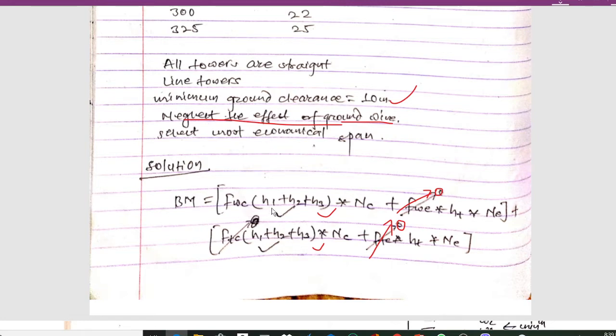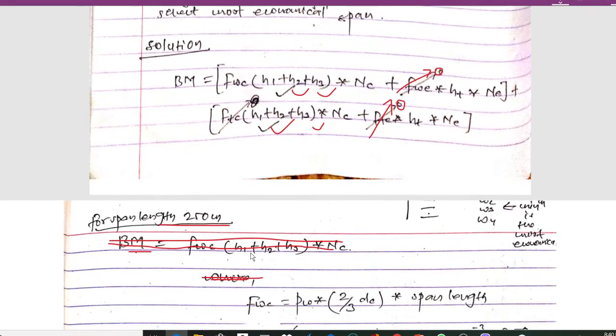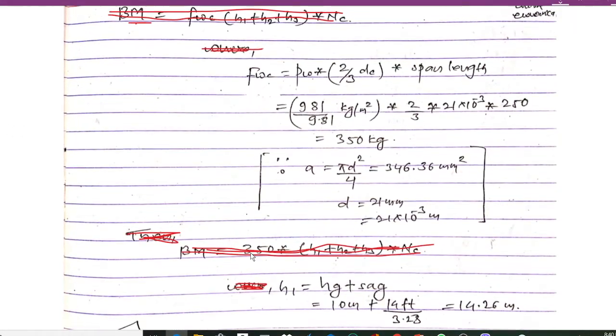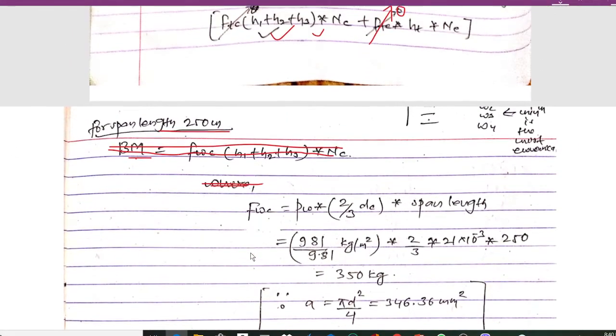The bending moment formula is: Fwc × (h1 + h2 + h3) × nc + Fwe × ht × ne + Ftc × (h1 + h2 + h3) × nc + Fte × ht × ne. Since we neglect the effect of ground wires, the Fwe and Fte terms become zero, and we consider only the Fwc and Ftc terms.